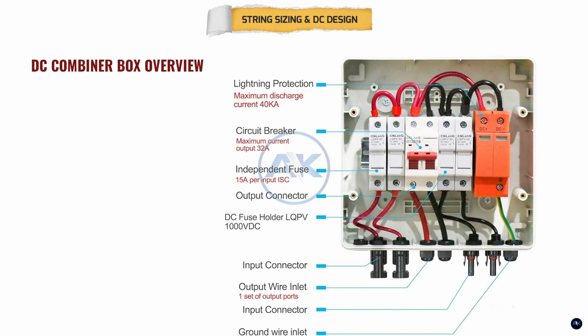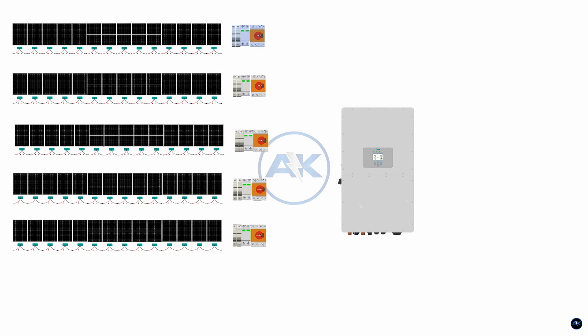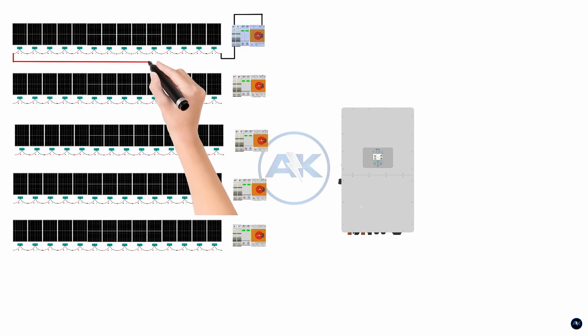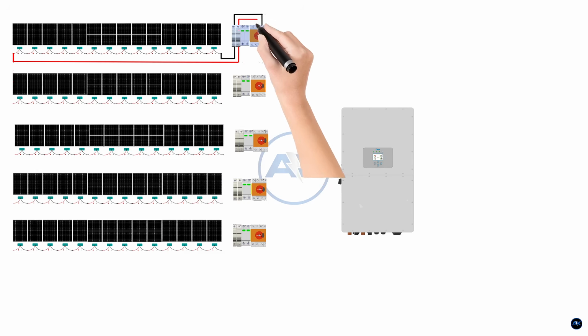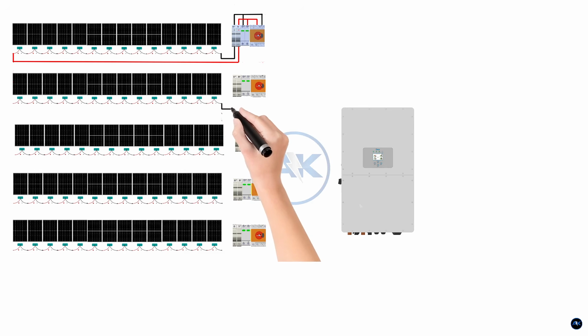With the string sizing verified and designed for cold temperature conditions, we can now move on to the physical installation of the solar panels. Section 4. DC side electrical connections. Panel strings to DC combiner box to 40 kilowatt hybrid inverter. Now we'll connect the DC side of the solar system step by step, starting from the panels and ending at the inverter. We are using 70 600-watt solar panels. These are divided into 5 strings, with 14 panels connected in series in each string.